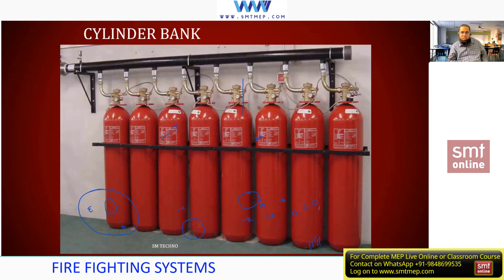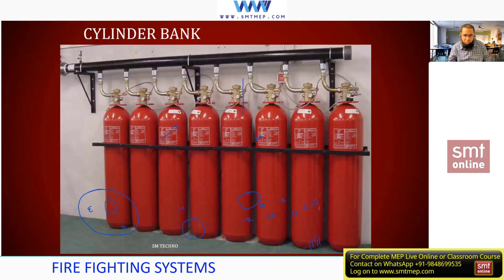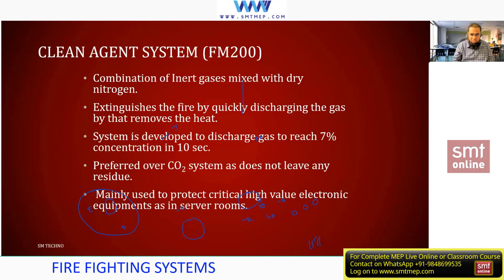An important point about CO2: it cannot be used in occupied areas. It can be used in unoccupied areas like battery rooms or equipment rooms without any occupants, because it is toxic. Regarding the use in server rooms: if there are no occupants, or if there is a separate alarm so occupants can evacuate, then yes. For occupied spaces, we use FM200 or other clean agents. CO2 controls fire by increasing CO2 concentration, which decreases oxygen and reduces combustion. The basics of the fire triangle will be discussed later.